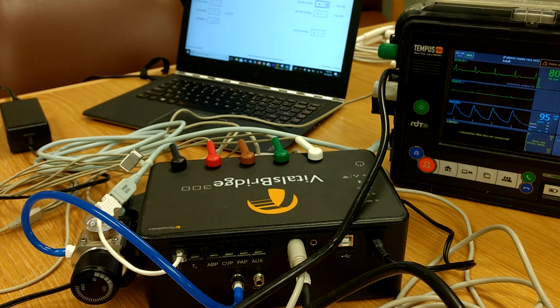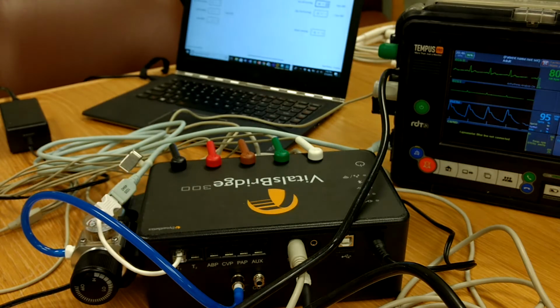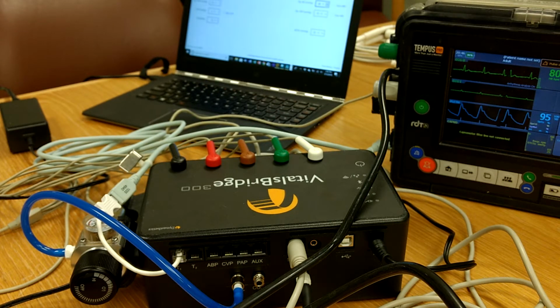And it'll go through. It takes a little longer now because it goes up to a higher pressure and steps down lower and lower looking for the pulses. And again, it's the amplitude of the pulses, the relative amplitude of the pulses for each given cuff pressure that determines the measured arterial blood pressure in the simulated cuff. There it goes, and now I've got a lower blood pressure. So that's non-invasive blood pressure.